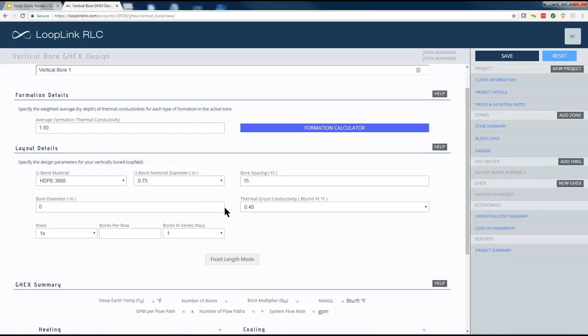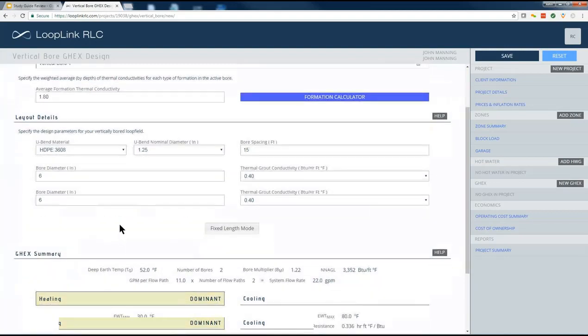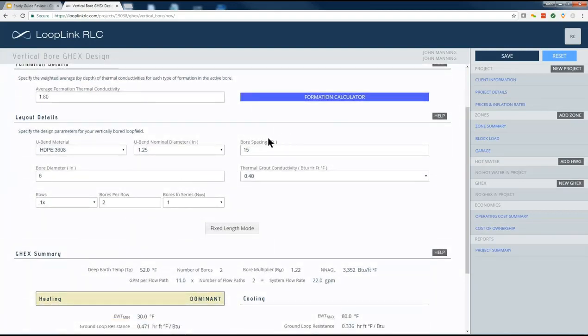So knowing that, we've got a 4-ton unit in the space. We've got a 3.5 ton unit in the garage, so 7 tons or so. What I'm going to do, for the sake of example here, is go to a 1.25 inch loop. You have to enter in a bore diameter. Generally, it's going to be between 4 and 6 inches. It doesn't greatly impact the calculations that much. I'll just pop in 6. And based on the rules that I just gave you, I'm going to try to get away with 2 bores here, 2 bores, spaced 15 feet on center with a 0.4 grout conductivity value.